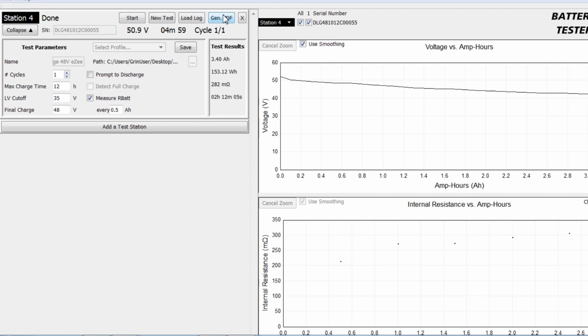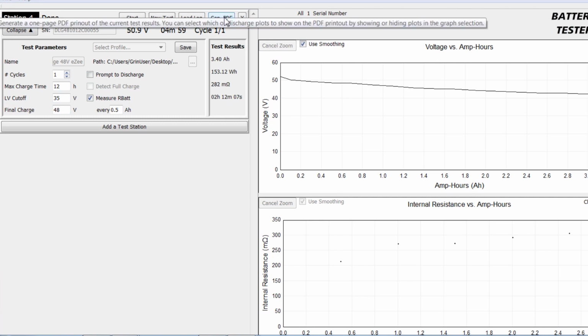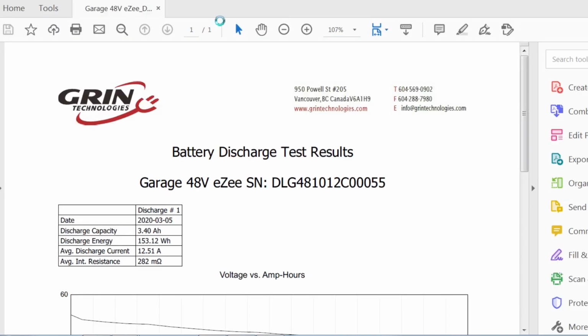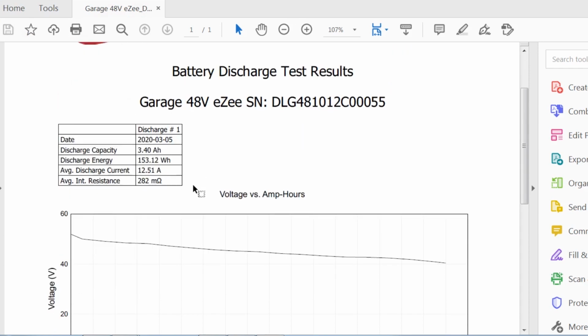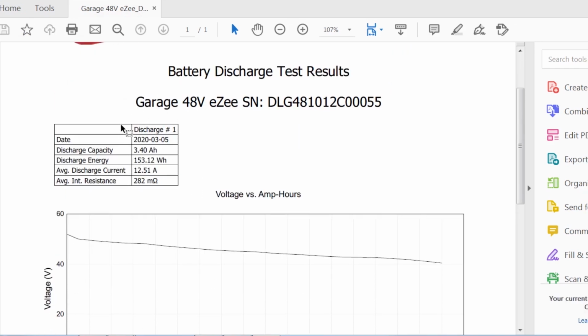What the Grinspector can do now is generate a PDF print report of this discharge test. If you click the Generate PDF button, it automatically generates a summary of the test results. Here we only did one discharge, which gave us 150 watt hours, 3.4 amp hours, and you can see where it cut off, with the battery at about 40 volts.